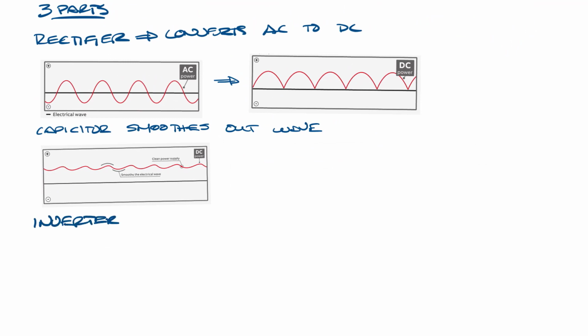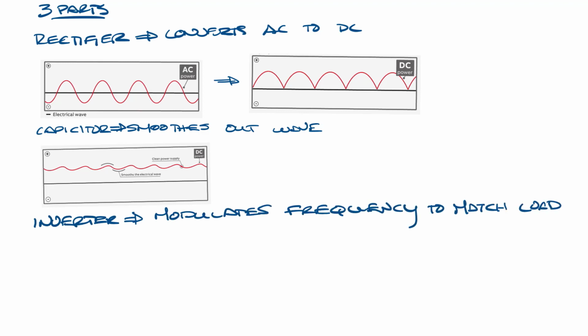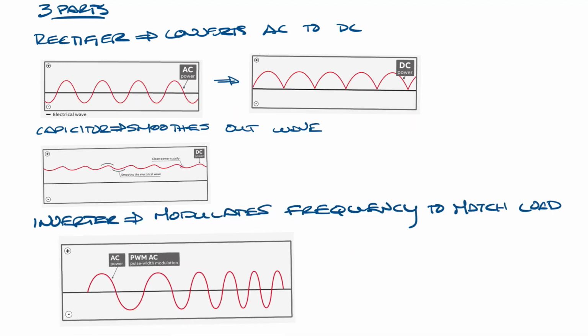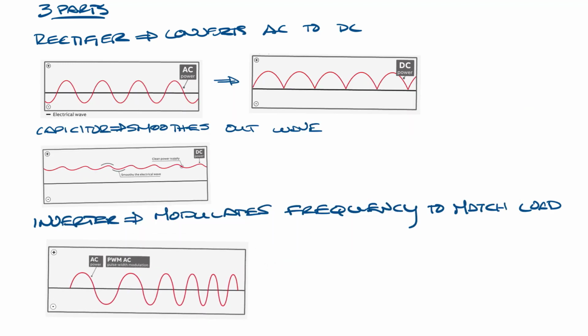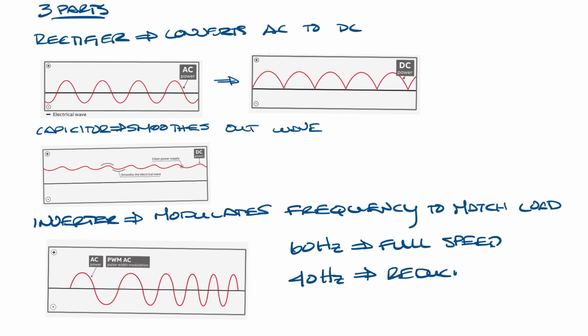Then this DC power flows to the inverter, which changes the DC output back to an AC power that goes to the motor. This also allows the drive to adjust the frequency and voltage that feed the motor based on demand. So if it sends the original 60 Hz signal, then the motor operates at full speed. But if it sends, say, a 40 Hz signal, it'll operate at a slower speed. This means that you can run your AC motors at the speed needed to match your demand load. So that's what VFDs are and how they work.